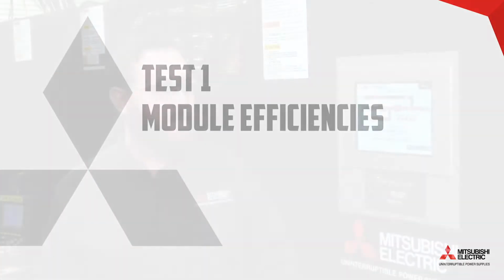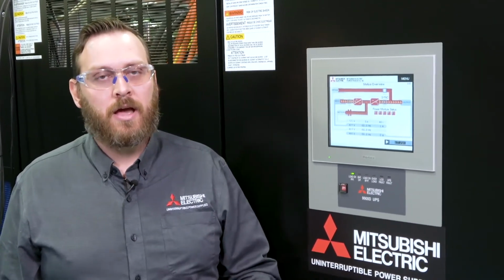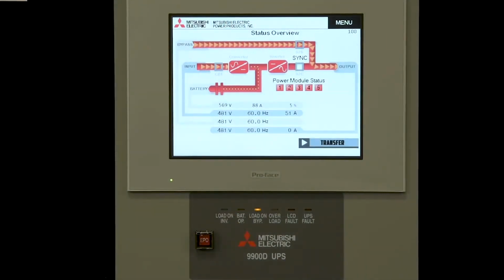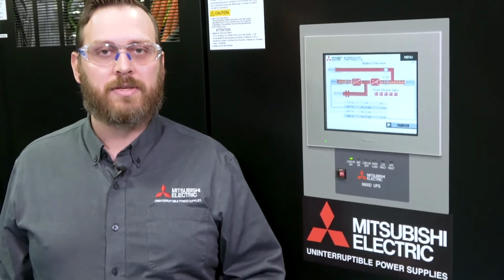So now that we're back to the main screen and the UPS is operating normally, we're going to begin with the UPS efficiency tests, and we're going to remove the battery source during this test, since obviously we have it in a charged state, so there's a decent amount of power going to that. And with the efficiency mode, we want to show you purely input power versus output power going into the UPS and out of the UPS, and show you how the system operates under those loads.